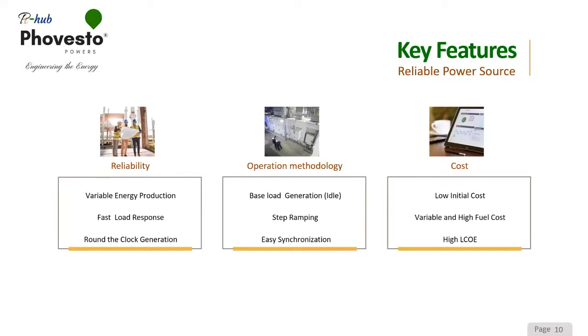Synchronization is very good with these power plants, around 30% of the load response is carried out without any controller for the higher rated DGs in the market. The initial cost of a DG or CHP plant is very low, but costs keep increasing because we use fuel, which isn't free like renewable energy. These plants use fossil fuel or biomass as continuous feed, which leads to a higher LCOE, higher per unit production cost.